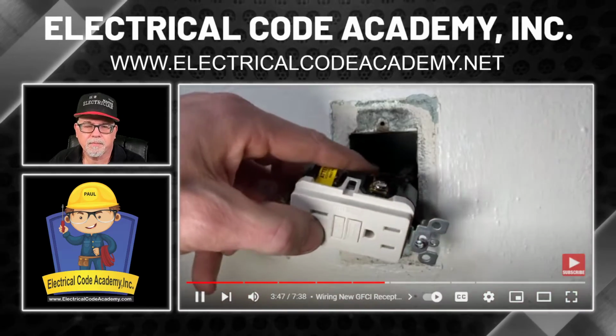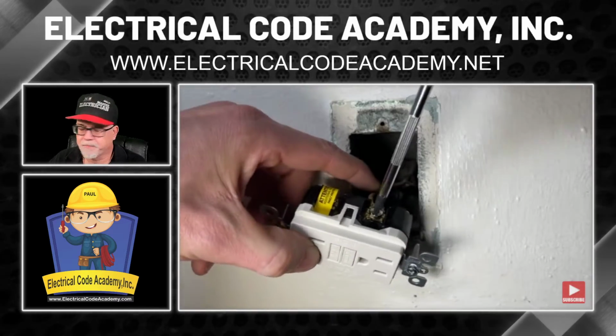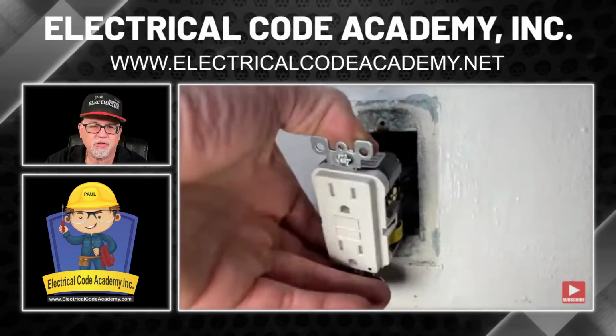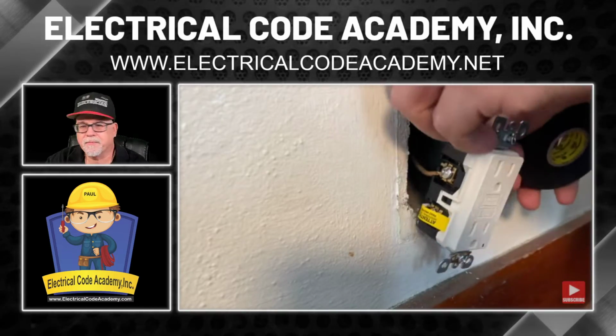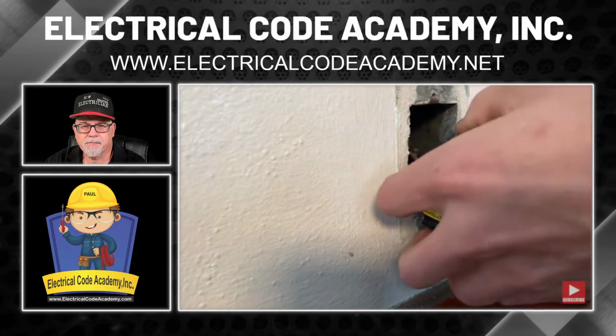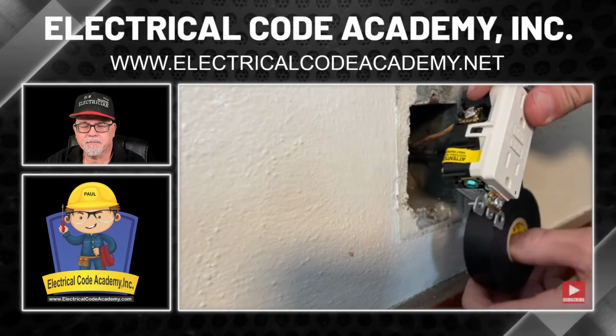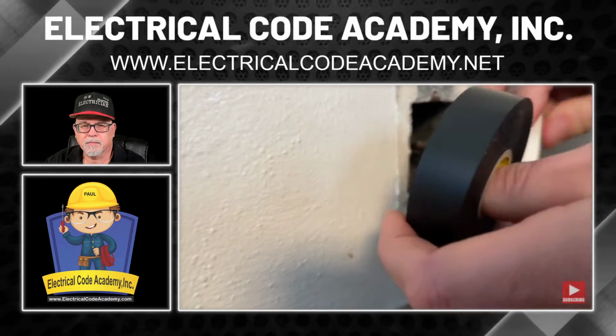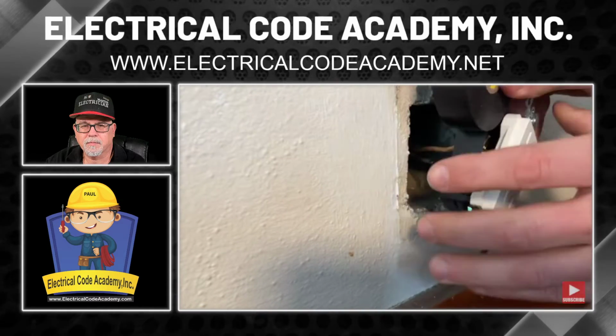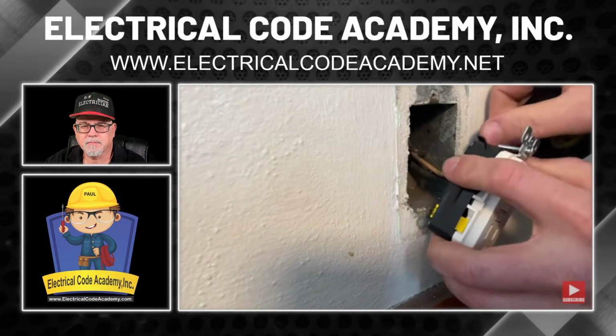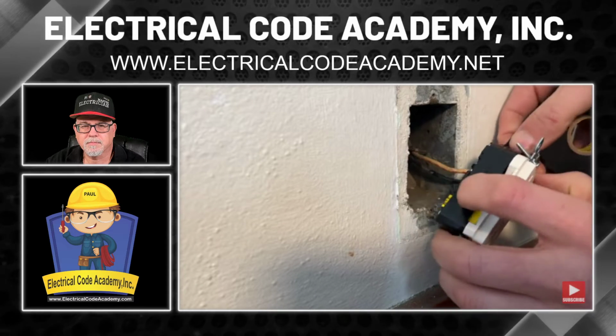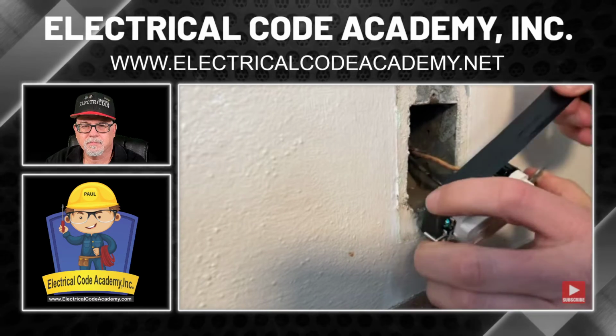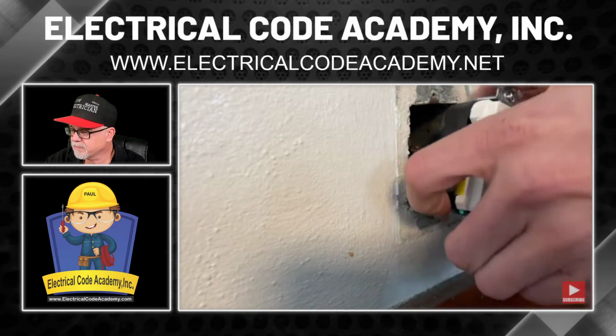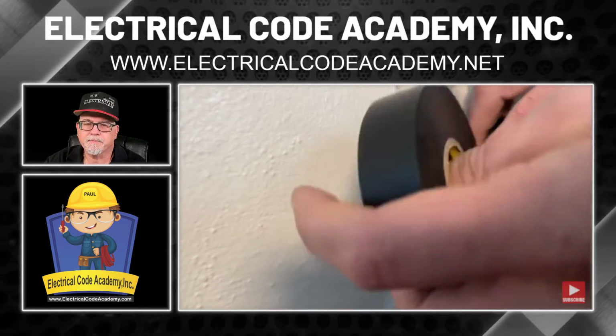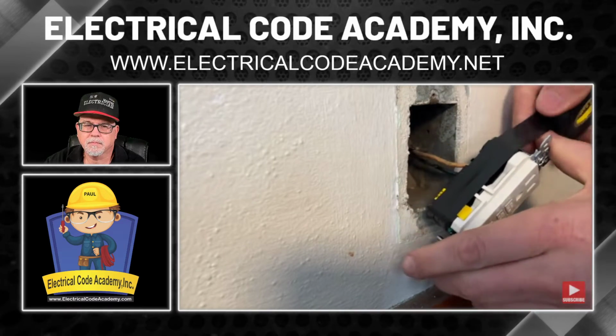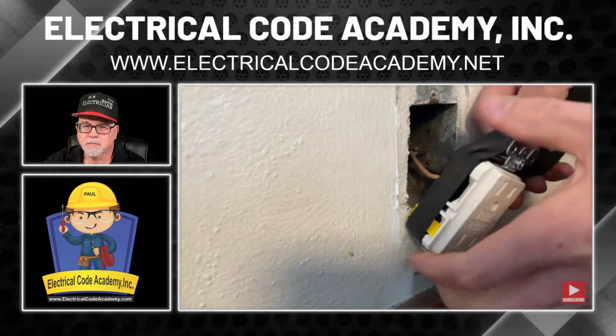Underneath the plate, making sure no exposed copper is going past the housing. Notice how there's hardly any room to work with. Before placing a GFCI outlet in the metal box, because it's so tight, I'm actually going to wrap it with 3M Super 33 Plus electrical tape. Best tape on the market. You can see the link in the description, which will show you exactly what I use. I'll do two wraps, stretching the electrical tape as I go on the outside. That will help bond the tape and also contour to the receptacle housing.